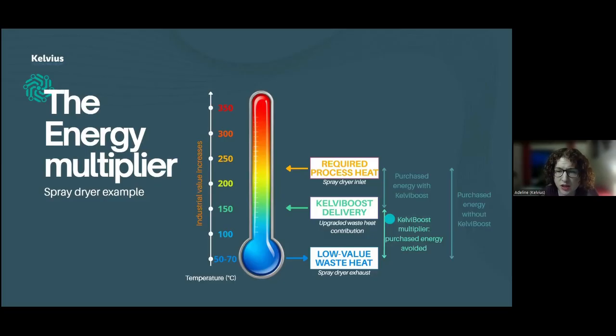Because we're able to recover and upgrade the exhaust of the spray dryer, we can provide a temperature up to 150 degrees—I'll show how that works next. 150 isn't enough to cover what they need since they require 220, but we'd be able to provide between 50 and 75% of the airflow rate needed at the inlet. Basically, we act as a baseline for process heat production, and they need to top up the remaining flow rate and temperature.